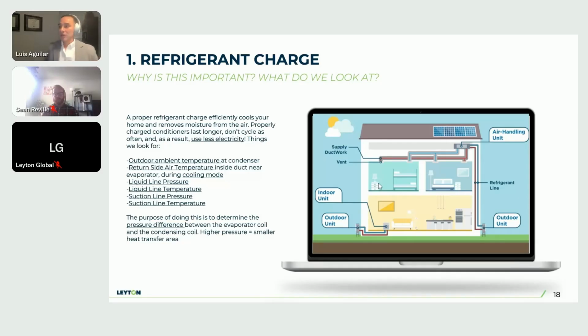All right. So the refrigerant charge. This is one of the overlapping things that are checked for single family as well as multifamily. And that's one of the checks that we do on site to ensure that the AC unit is conditioning how it's supposed to condition. I always like to bring up the story of having an AC tech come over, and one of the things that they always suggest is that you need more refrigerant, and they add refrigerant to your unit, and then everything's working again, right? The AC feels cool again, and then you can get back to doing what you're doing. So it's a very common issue, as you can imagine.